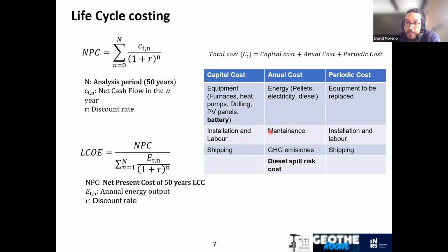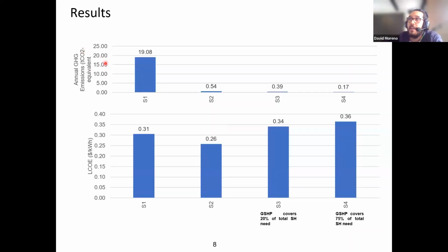As Abra said in her presentation, it's pretty common that there are diesel spills in Nunavik, small diesel spills sometimes, but over time they become big amounts of diesel spills, and the cost of soil remediation is very high. So it's very important to take this into account in the economic analysis, so we established a diesel spill risk cost. For periodic costs, equipment has to be replaced because it's a 50 year analysis period. So at the end, here I have some of the results. In the first graph we have the annual greenhouse gas emissions in tons of CO2 equivalent. Scenario one, where the heating needs are covered only by the diesel furnace.